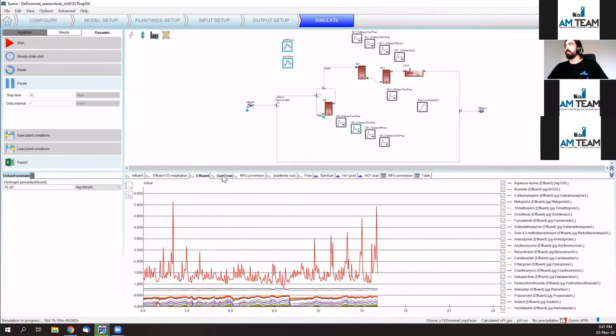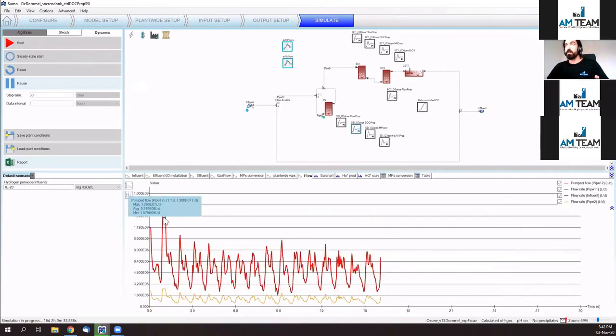But you can also check the UVA fraction that is exiting the plant and the overall effluent at the outlet of the whole plant site. So what I was talking about, you see this red line here is where the bypass kicks in. This is a reasonably small rain event, but which caused a sufficiently high flow to get bypassed here. And here is the capacity of the ozone installation treating all the flow during the rest of the days.